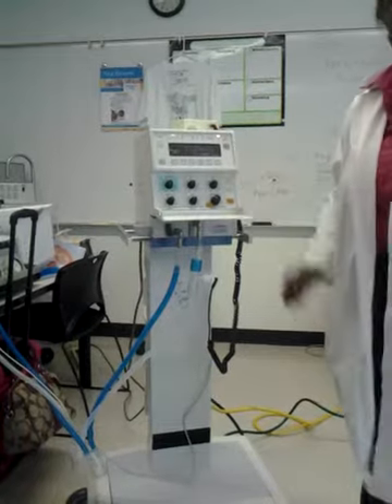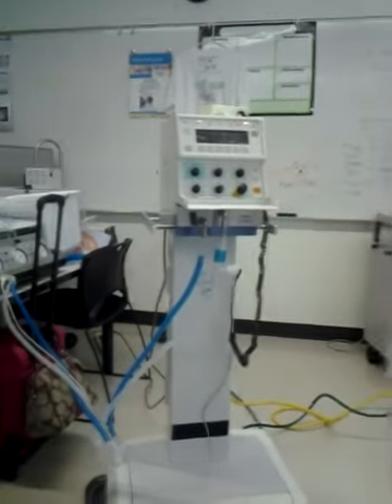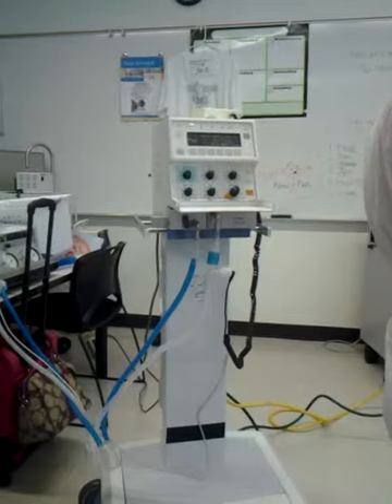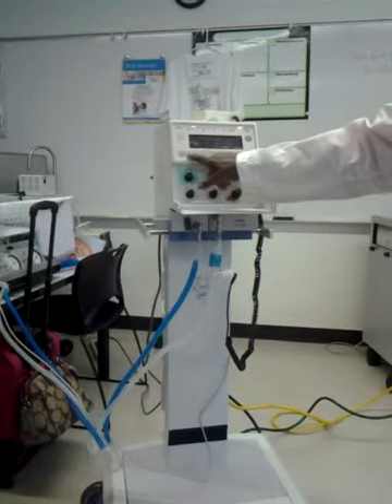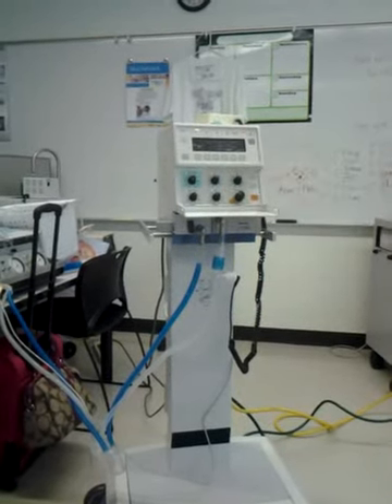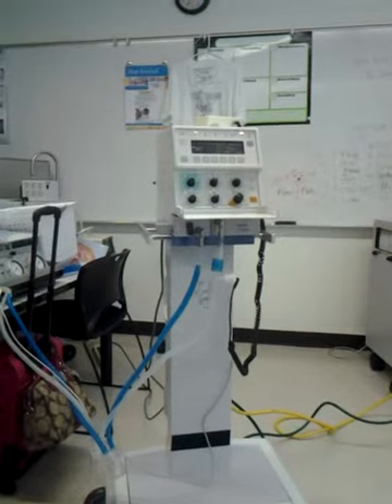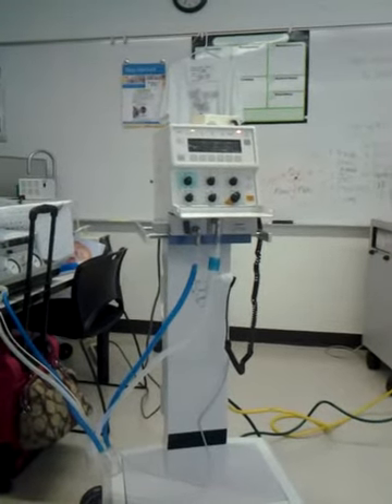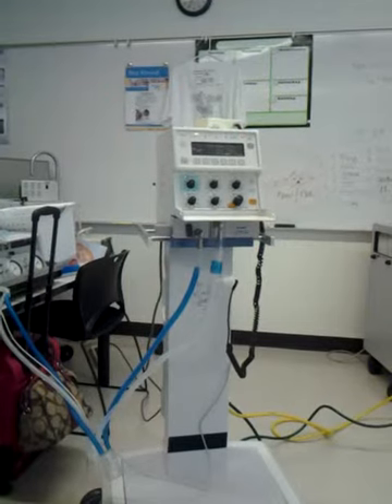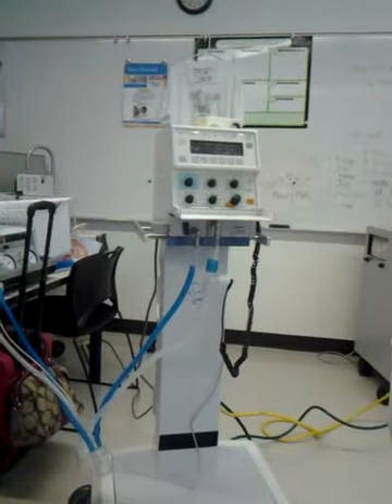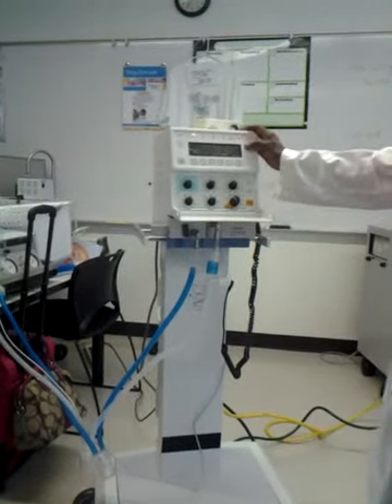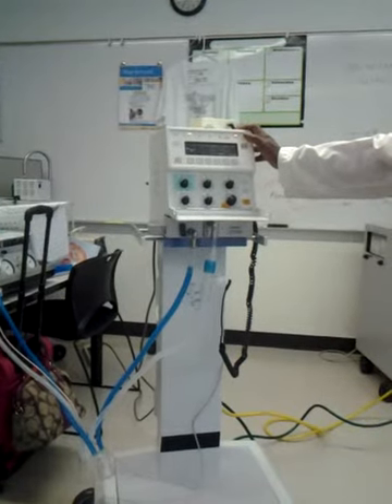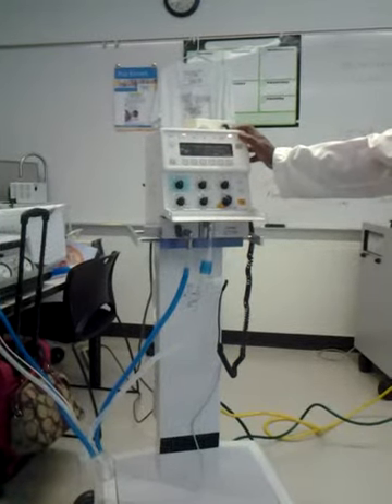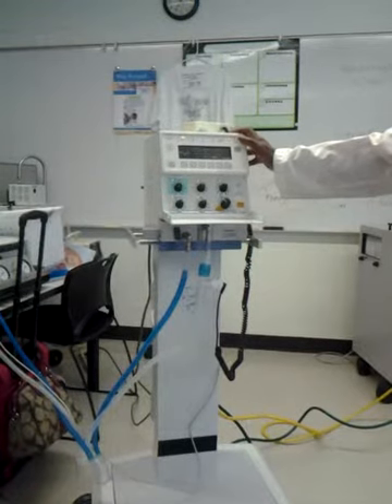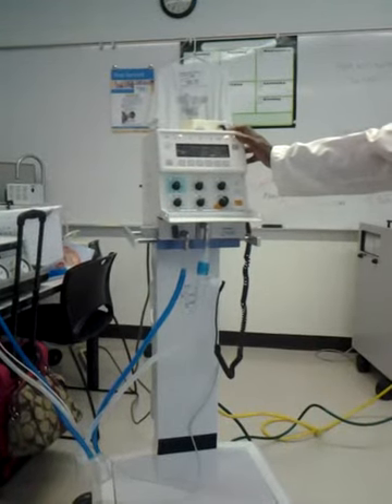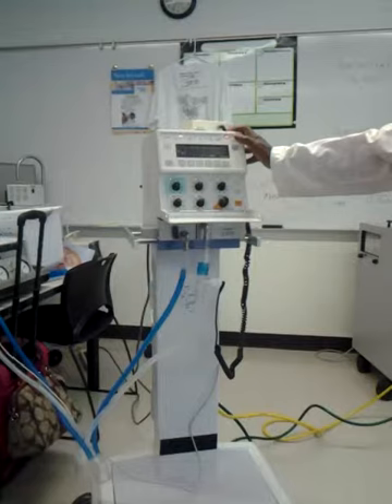What mode are you in right now, ma'am? When you go into the assist control mode, you can use a thing here called volume guaranteed. She told us today, don't use the assist control. But it's used sometimes, so you have to know each mode. You have to know all the modes. Exactly. But the assist control on this isn't like the assist control on the 840. The assist control on this is more like the A/C on Servo, which is what they use in the NICU. Why were you told not to use assist control on it?